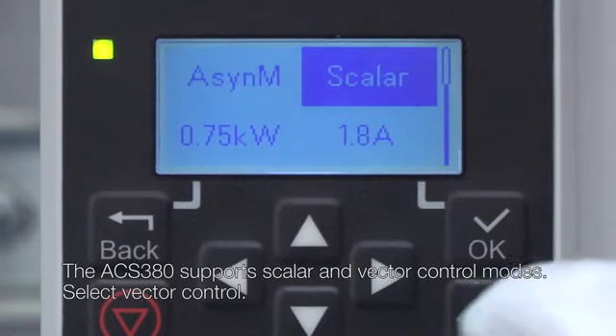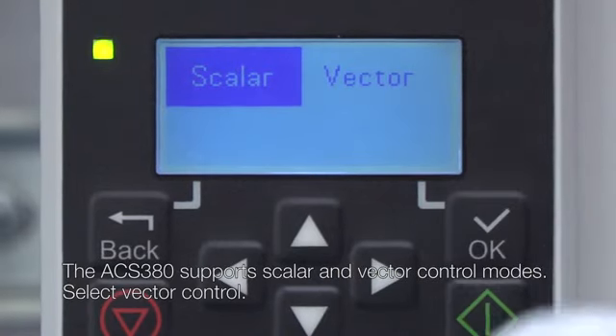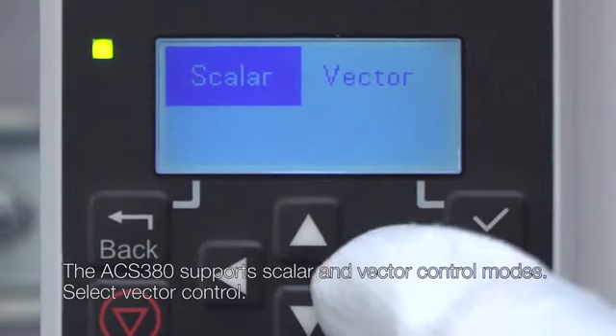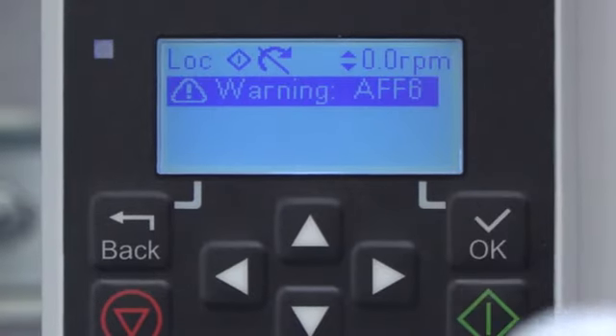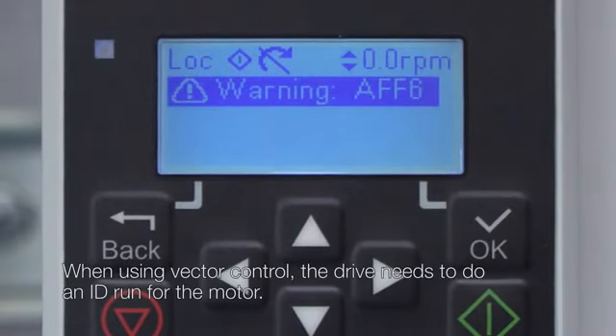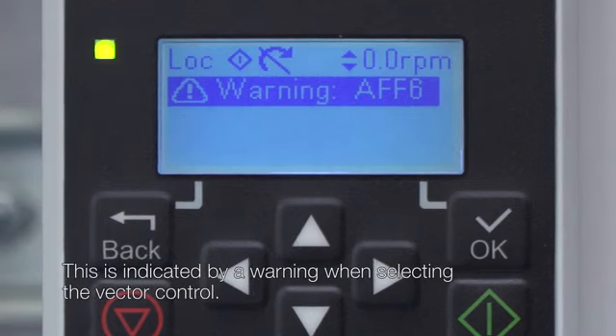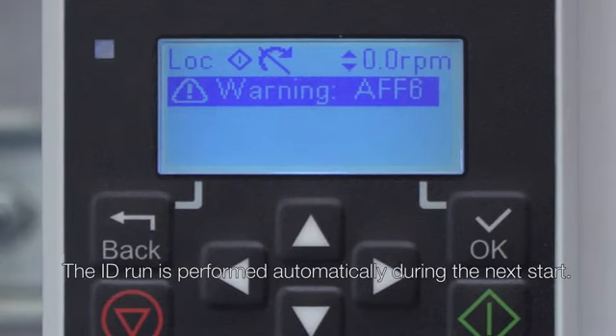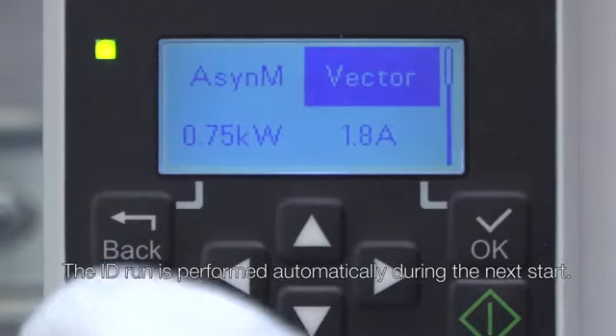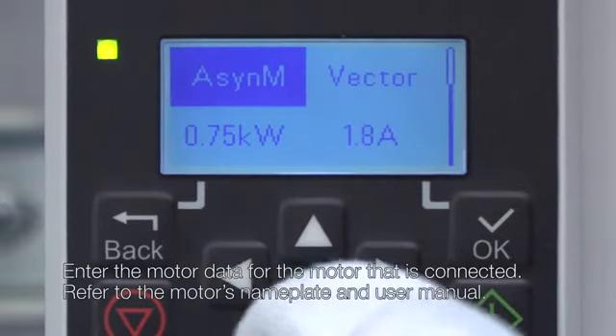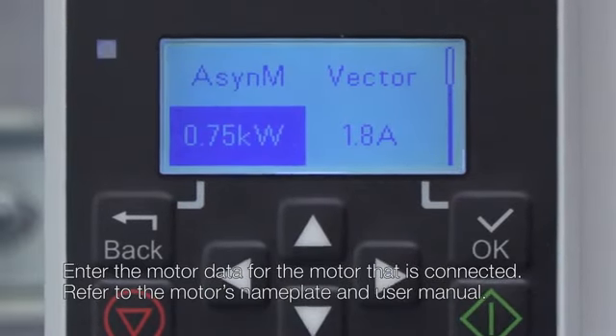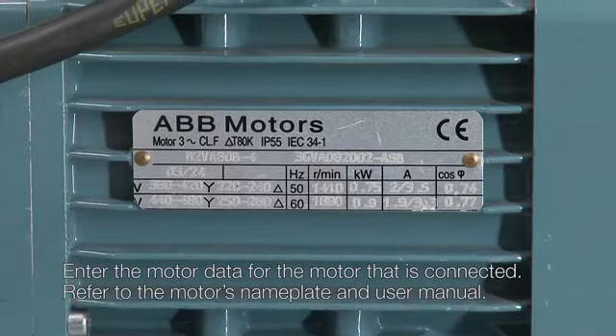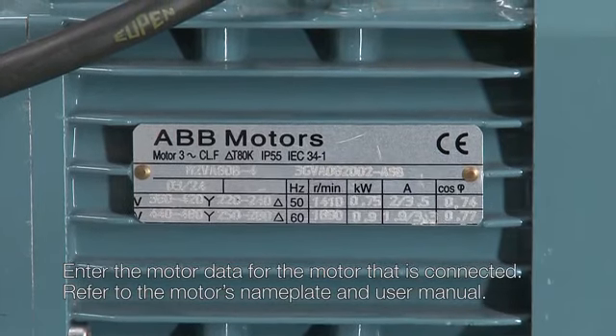The ACS380 supports scalar and vector control modes. Select Vector Control. When using vector control, the drive needs to do an ID run for the motor. This is indicated by a warning when selecting the vector control. The ID run is performed automatically during the next start. Enter the motor data for the motor that is connected. Refer to the motor's nameplate and user manual.